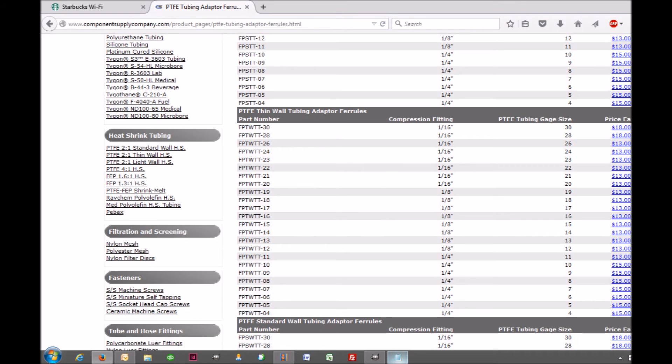If I was working with a different gauge size, I would need to determine the appropriate ferrule size and accompanying compression fitting. For example, to incorporate 20 gauge thin wall PTFE tubing, I would need to use a one-sixteenth inch compression fitting. Therefore, the part number of the ferrule I would need would be FPTWTT-20.